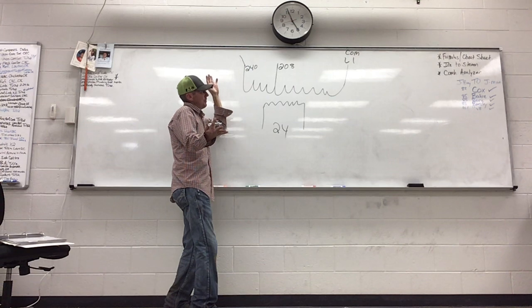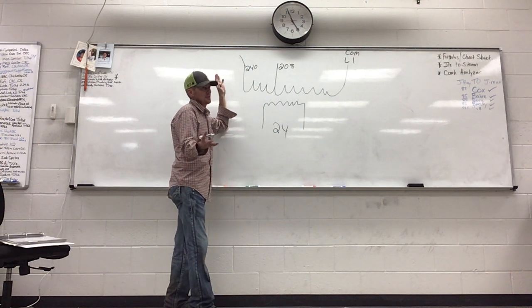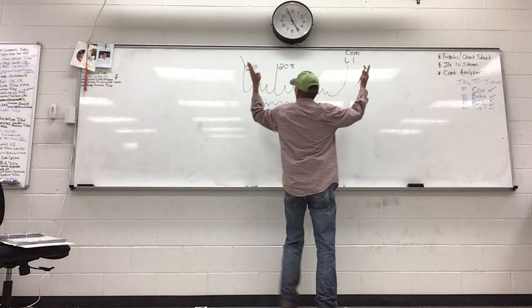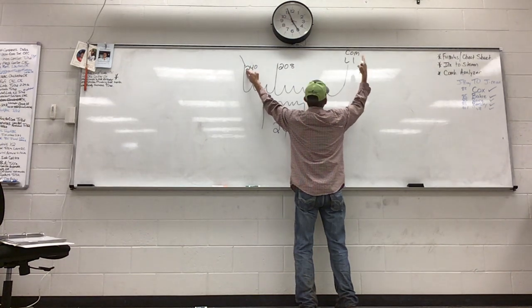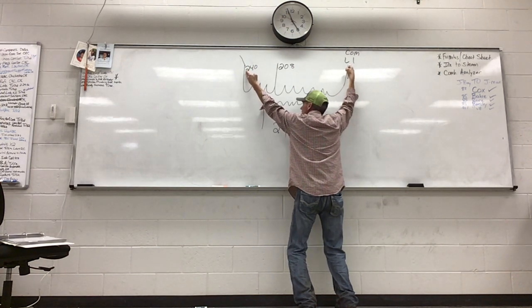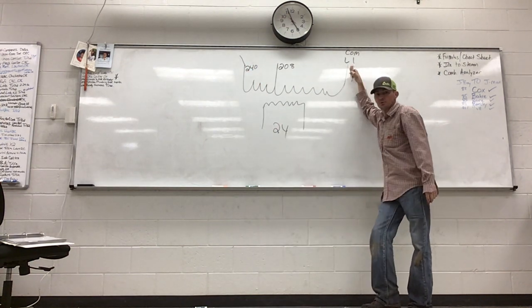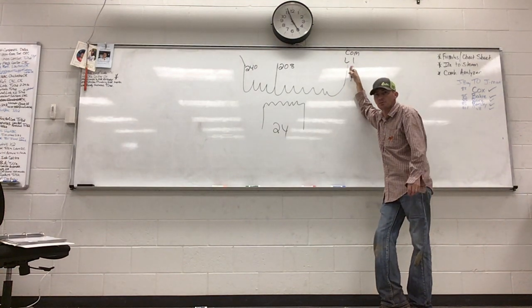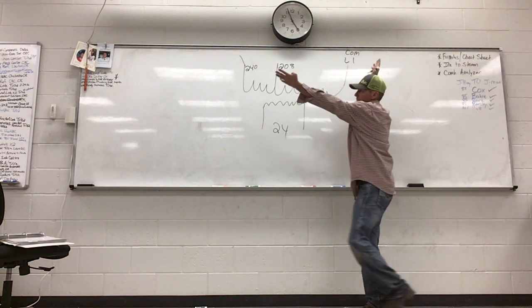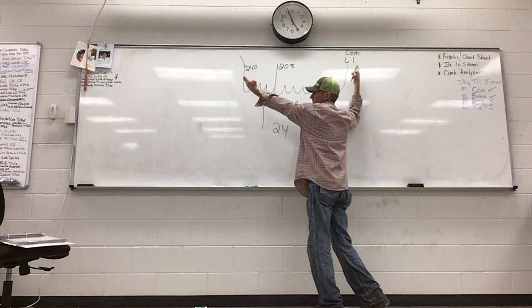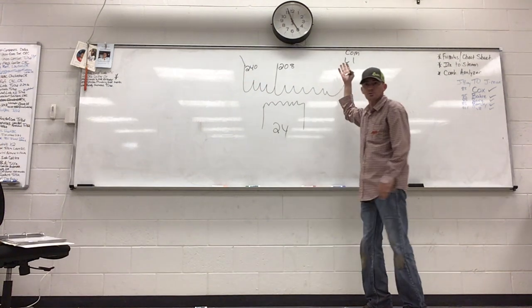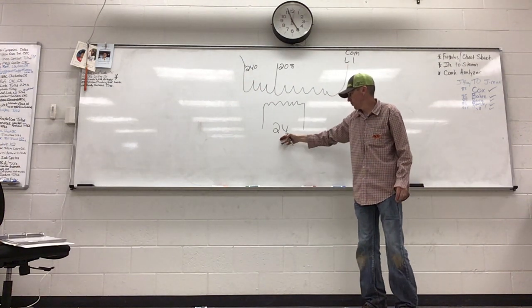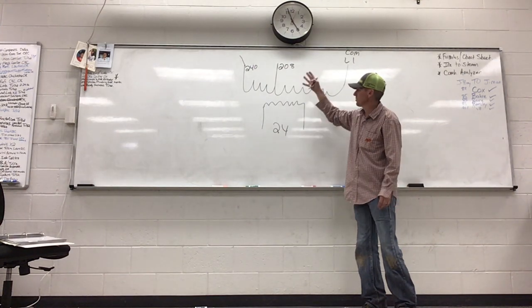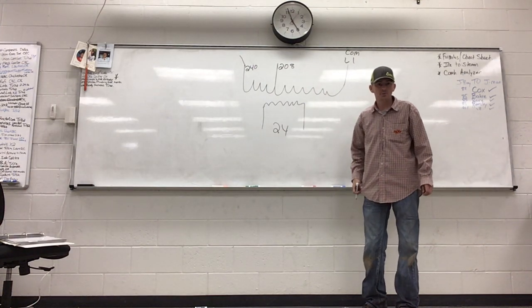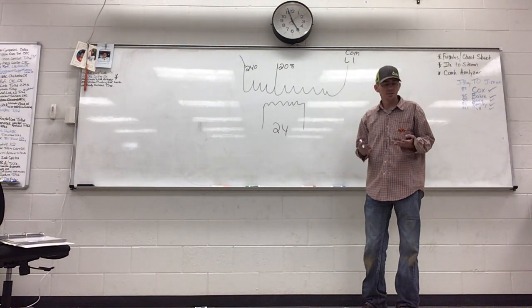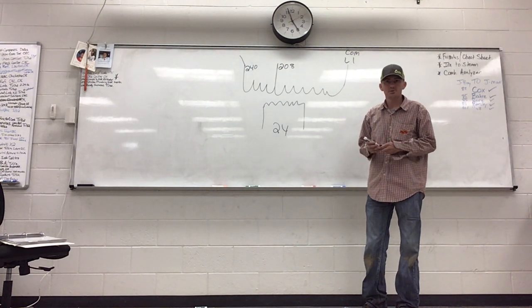So what happens, you guys obviously know this, but what happens if I have a 240 primary, but I only apply 208 to it? What's going to happen to my secondary voltage? It's rated for 240 primary, that's the way it's wired from the factory. I only apply 208 to it. So my 24 is not going to be 24. We can do the math, it would be something around 19, 20 volts, right? And so you potentially could start getting some chattering and some other stuff going on.